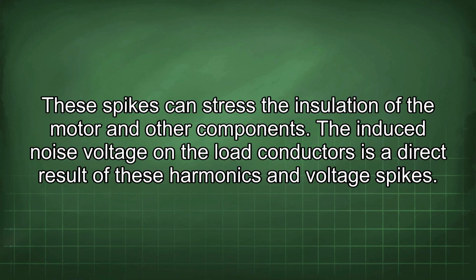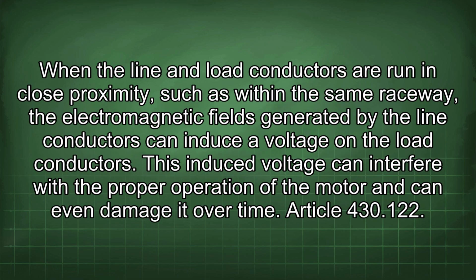The induced noise voltage on the load conductors is a direct result of these harmonics and voltage spikes. When the line and load conductors are run in close proximity, such as within the same raceway, the electromagnetic fields generated by the line conductors can induce a voltage in the load conductors. This induced voltage can interfere with the proper operation of the motor and can even damage it over time.